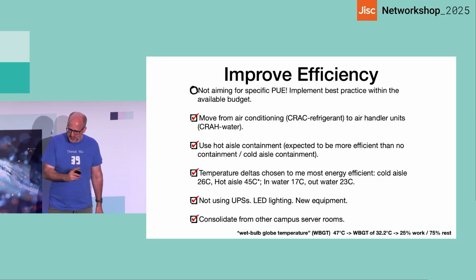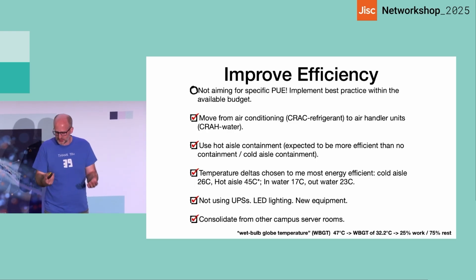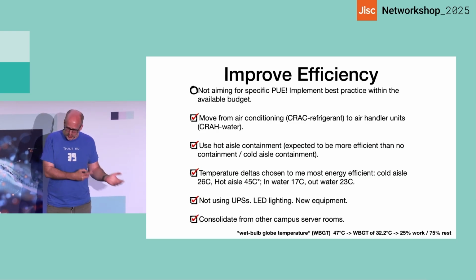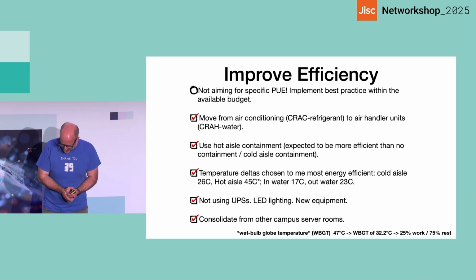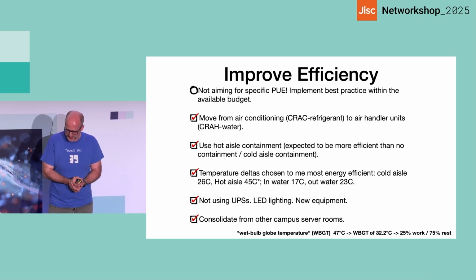We improved the efficiency. As I say, we didn't aim for a particular PUE in the room, but we aimed for using best practice, so hot aisle containment and such. We went from using refrigerant cooling to water cooling, so there's an improvement in that, but also that's good for the environment. Hot aisle containment, as I said, is considered one of the best solutions for this sort of build. We chose the temperature differentials, the temperature deltas, to be optimal for the cooling and efficiency. We do not have UPS in this room, and we do not have a UPS for the data center as such. If you need a UPS, you have to put it into the rack yourself. That's partly because, again, with the LHC, if we have a power glitch or we have to power down, we can cope with that because the slack gets picked up elsewhere. If you didn't have that flexibility, you would need to have a UPS room.